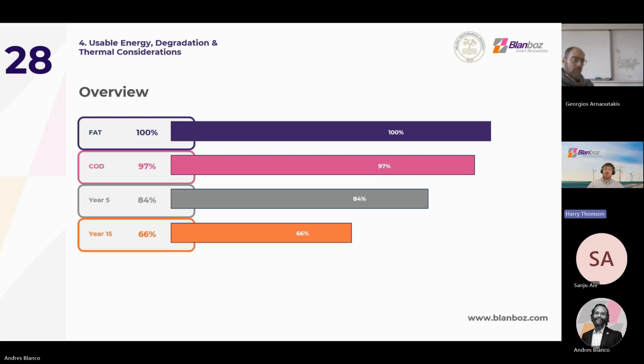Now we see the project when it's operating. In year 5, the BESS has been operating for 5 years at an average of 1.5 cycles per day. We now have degradation that's been caused through the use or the cycling of the BESS. And this continues to year 15, where the project is approaching the end of its life. Most BESS suppliers put a limit on their equipment, and that is after 60 to 65% state of health, the equipment should be disposed and recycled within the regulations of the country.